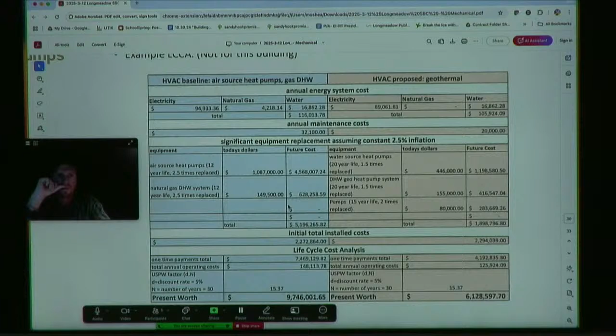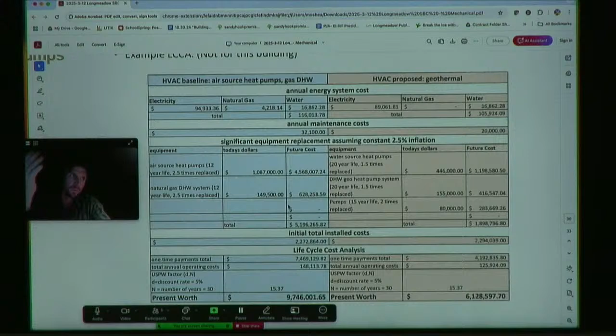I sum up the annual operating costs, and then I calculate a USPW, which is a Uniform Series Present Worth Factor. That's a function of D, a discount rate. I typically use 5% for most of these types of calculations, and the number of years, typically 30 years. If there's a standard that says 40, even better.